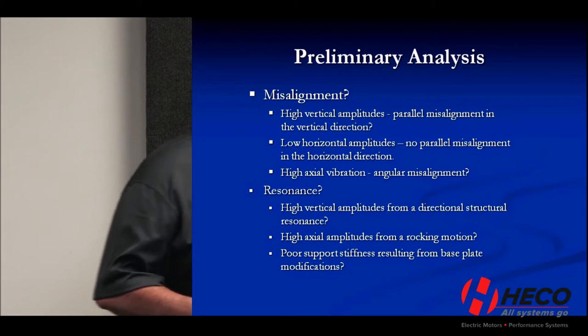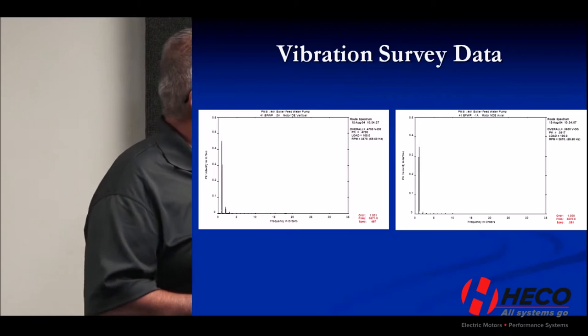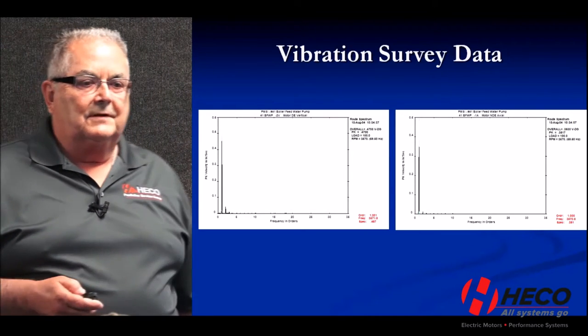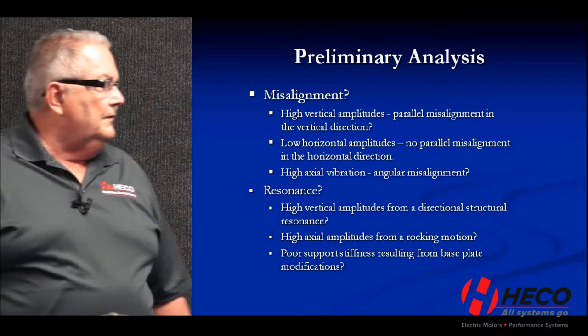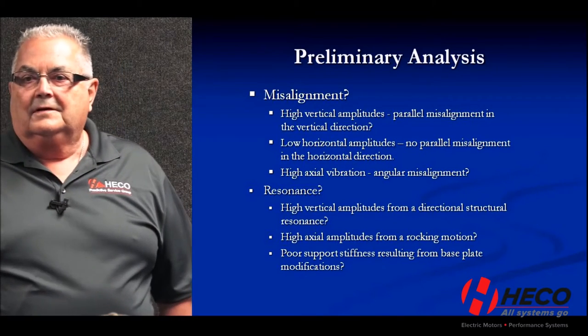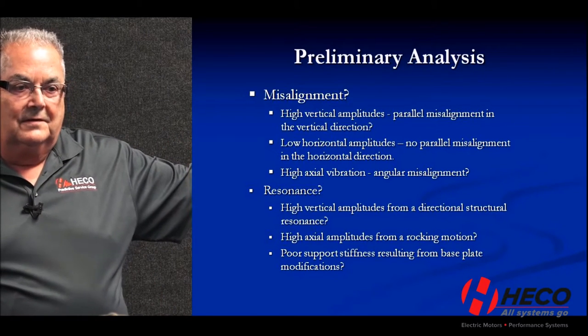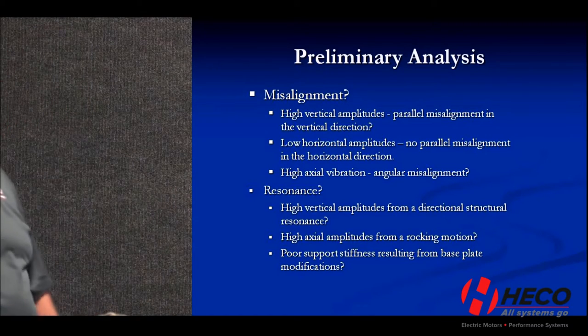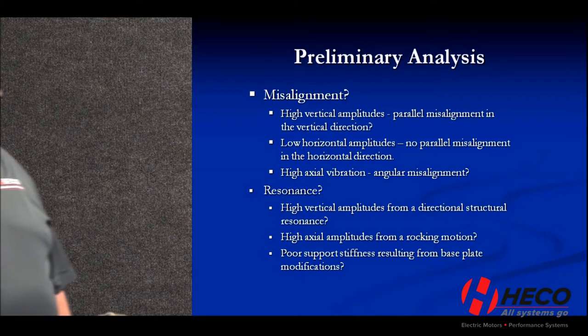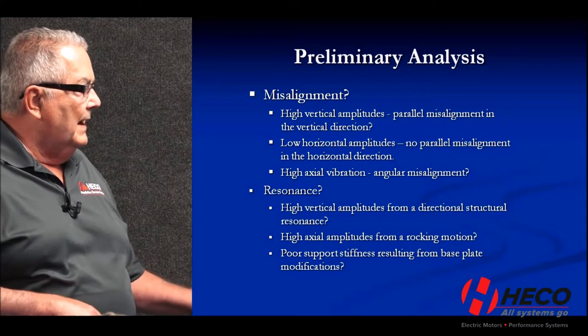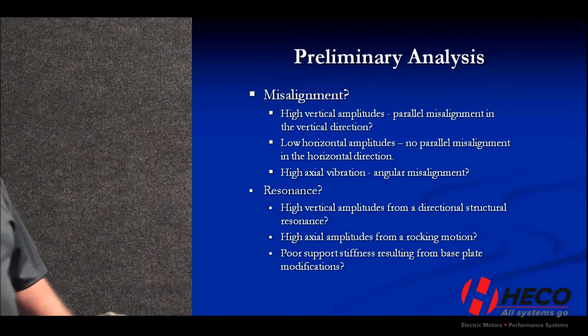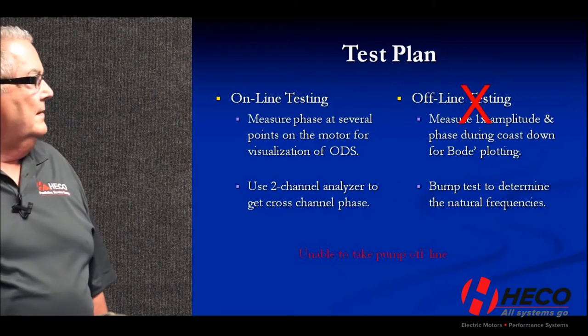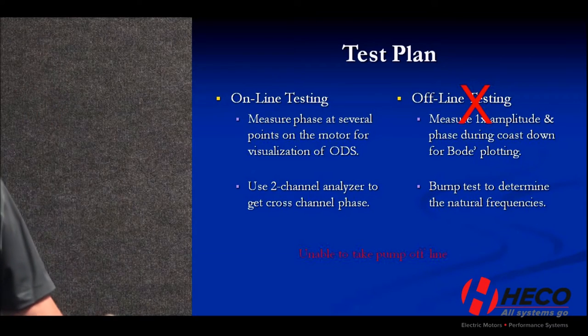There's a large difference between the vertical and the horizontal, and the axial is high also, but the vertical is much, much higher. So might this be a resonance situation? We noted that changes had been made to the structure, and also the motor is different — it could have a different mass than the previous motor. So we were pointing to this possibly being a resonance situation resulting from poor support stiffness in the base plate.